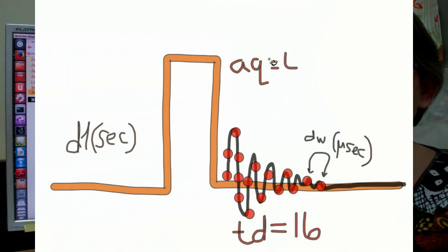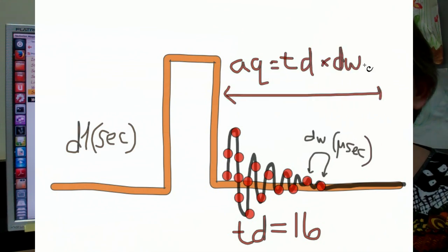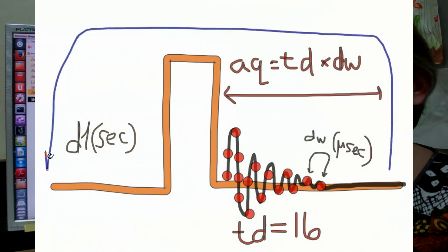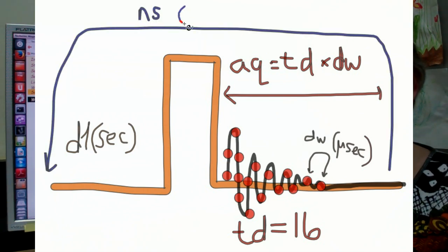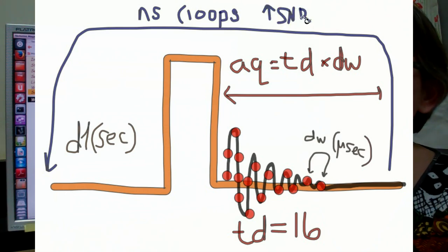Number 4, TD, the number of digitization points, which you'll adjust to control the time that the detector is on. And number 5, NS, the number of FIDs to be signal averaged in order to improve the signal to noise ratio.